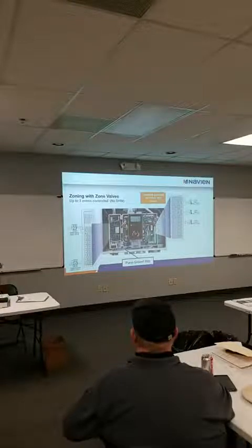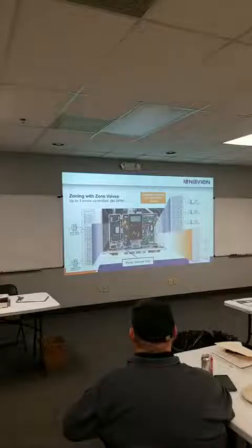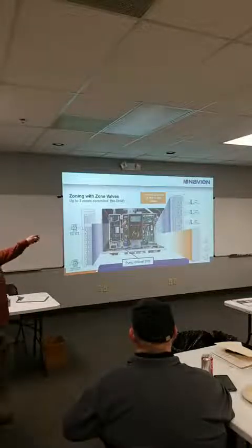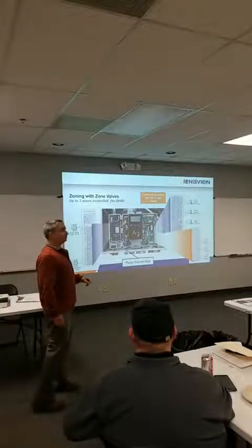So you will see on the zone valves that we max out at 3/4 of an amp there. So depending on the zone valves you're using, if you only have one zone valve and it's more than that, that's a cumulative. When you can add them all together. But that's kind of a limitation on the zone valve, right there. On all of them added together or each? So it would be, 2 1/4. Yeah.